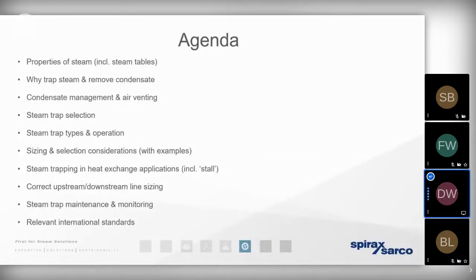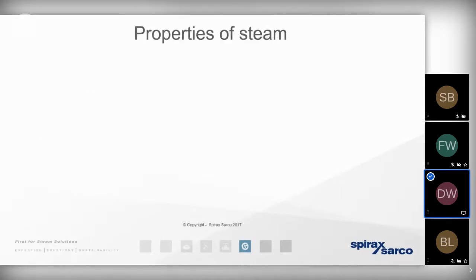So I want to start off with the basics, first of all, and I want us to fully appreciate what steam is and why we need to treat it completely differently to any other sources of energy, such as hot water or thermal oils. And that's because steam's a gas. And as we've mentioned in the previous presentations we've gone through, that gas is compressible. In other words, if we're generating and distributing that steam at a high pressure, the volume can be compressed, the benefit being we can distribute it in a small nominal bore pipework.